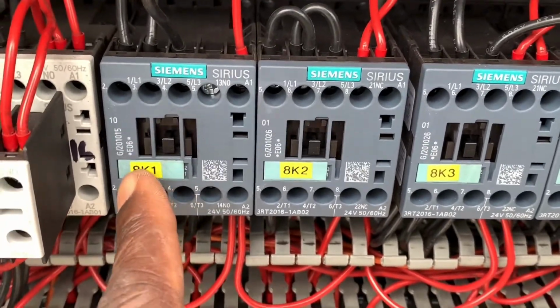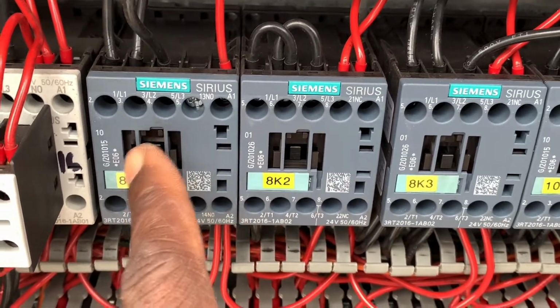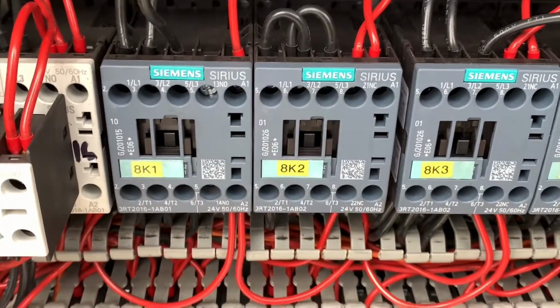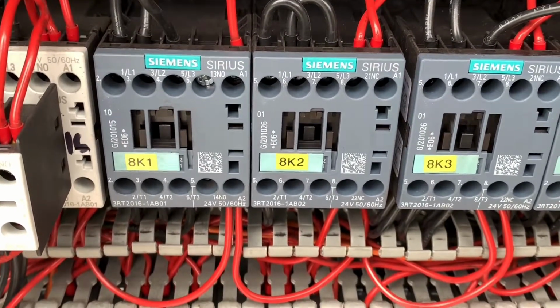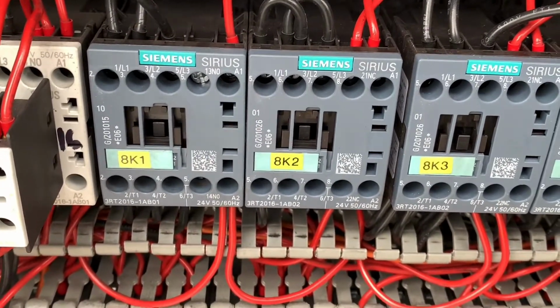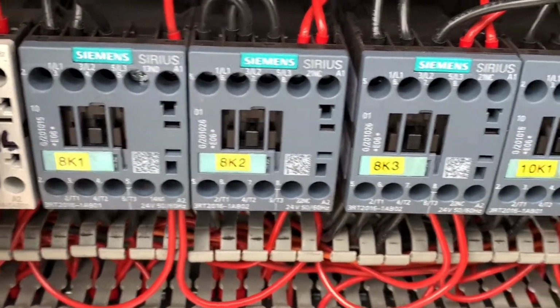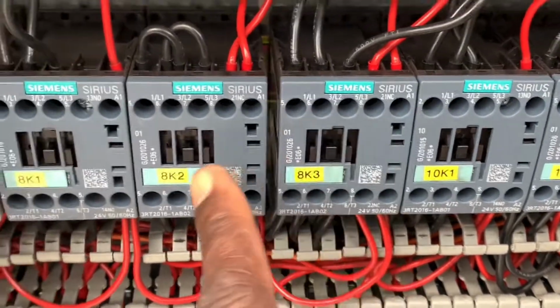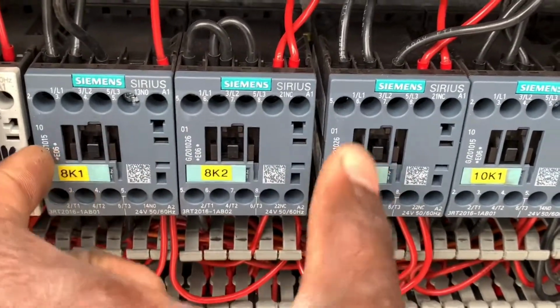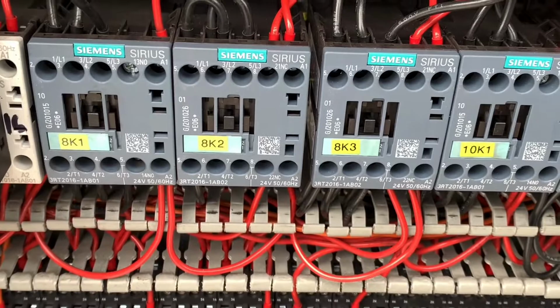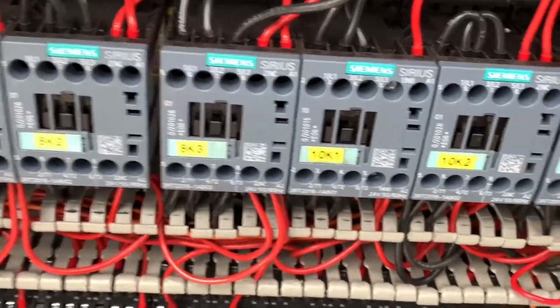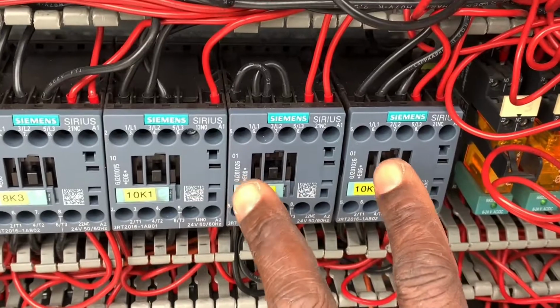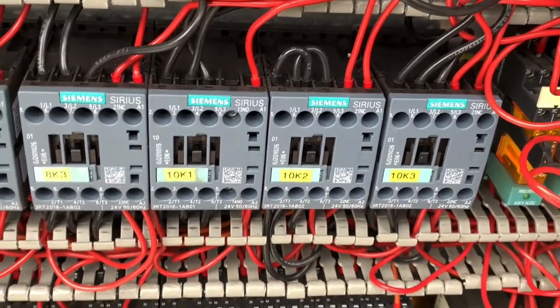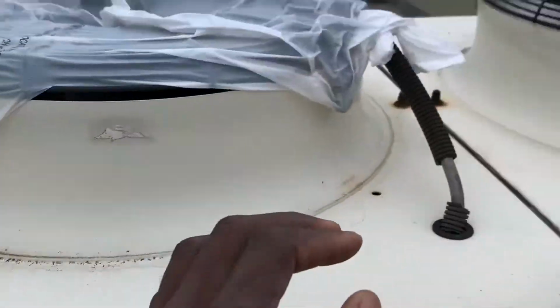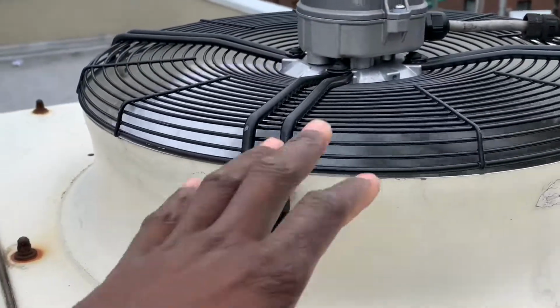Condenser fan. These two combined run the motor in the Y or star configuration, so it runs on low speed. And then this one and this one combined will run the motor in the delta configuration, which is high speed. And these other three over here are for the second circuit or second stage condenser fan. Both condenser fans are in parallel. They run together in pairs.